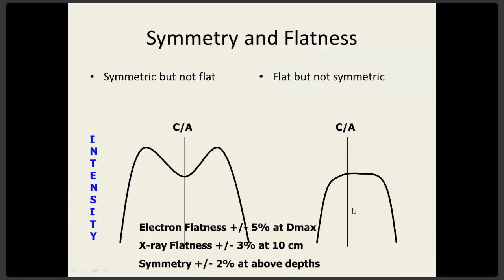That's not so much of a problem because a treatment planning computer can be modeled to represent this and show accurately what's going on in the patient. This is a much worse situation on the right. This is a beam that is flat, but not symmetrical. And this means that the beam has been missteered. And the treatment planning system will assume that the beam is symmetrical about the central axis, but the actual radiation treating the patient is not symmetrical. And that could be a very dangerous situation. So flatness and symmetry are monitored quite often in a radiation therapy department.